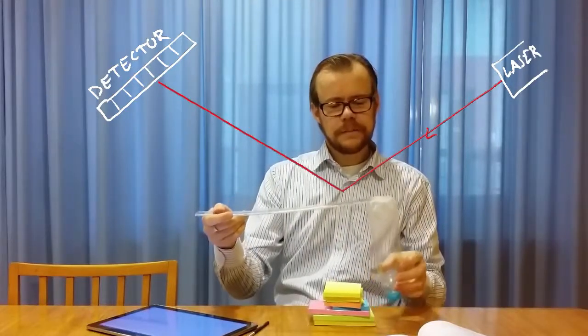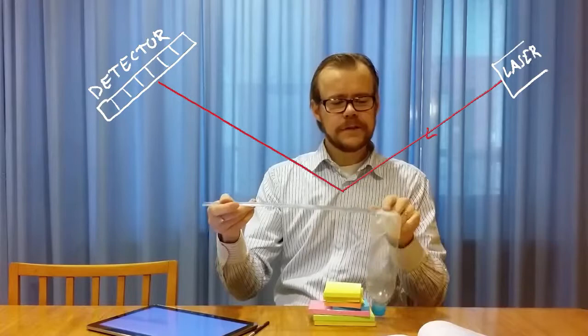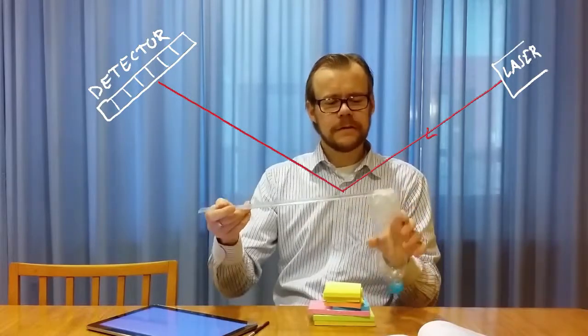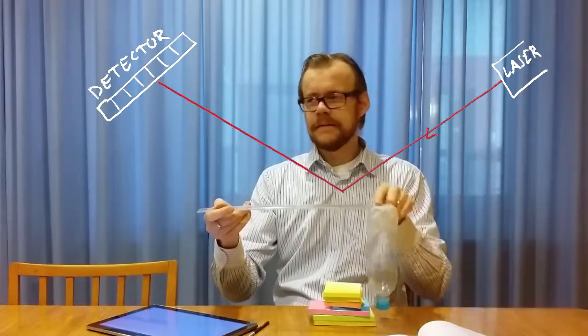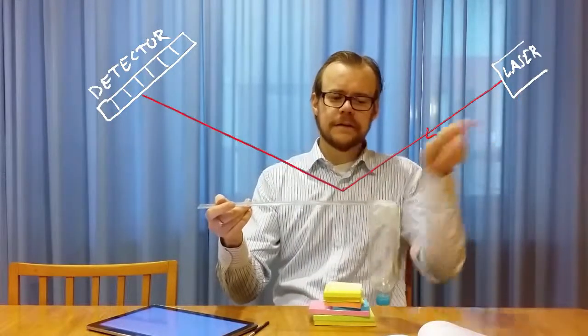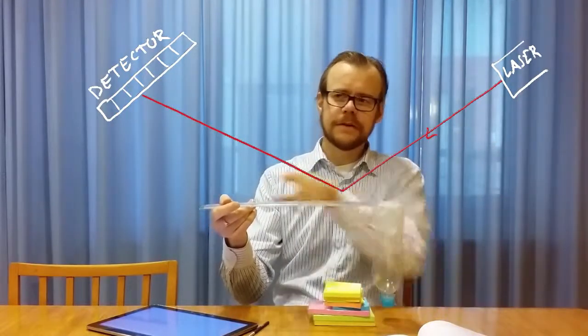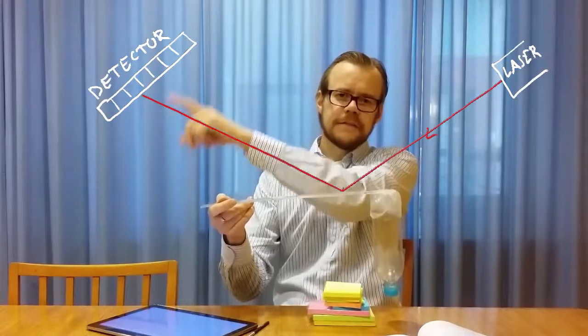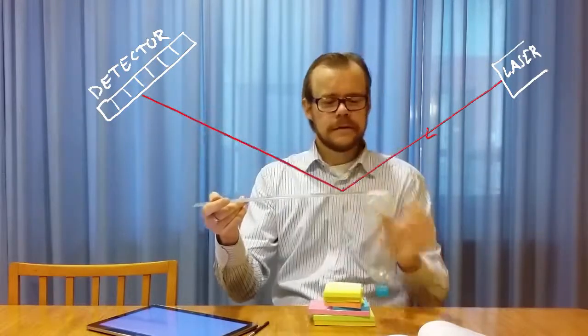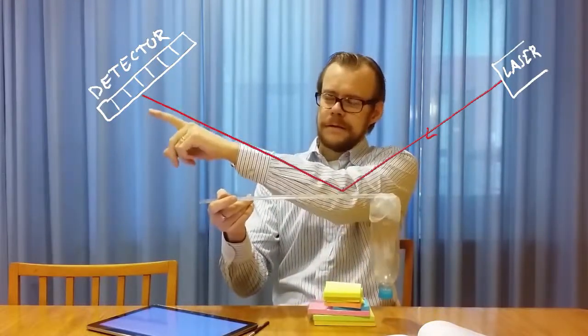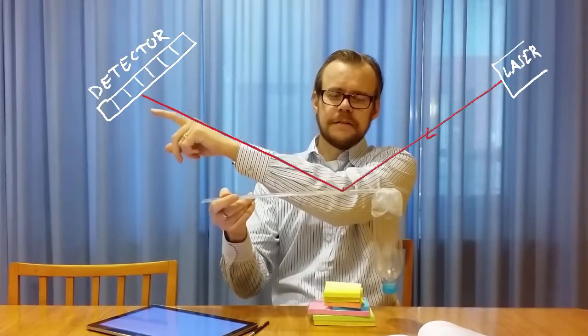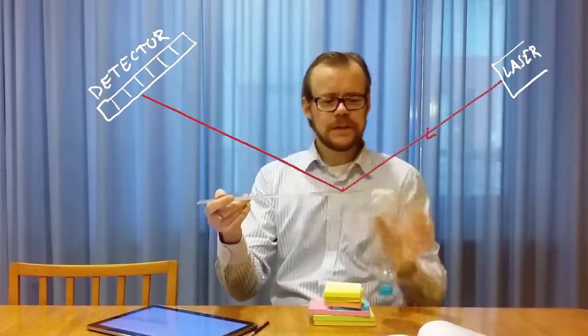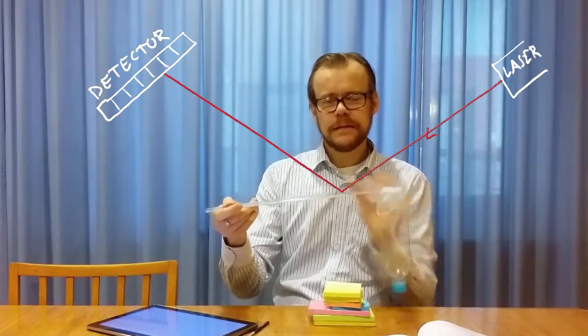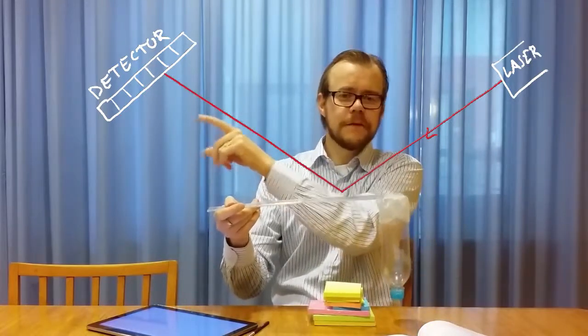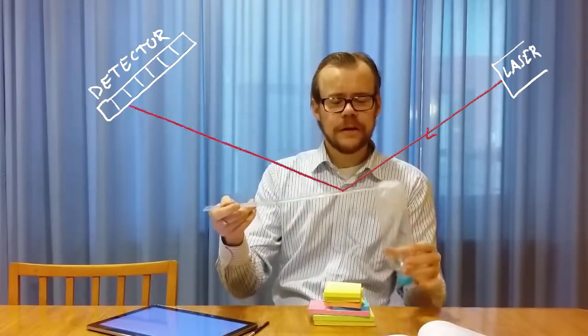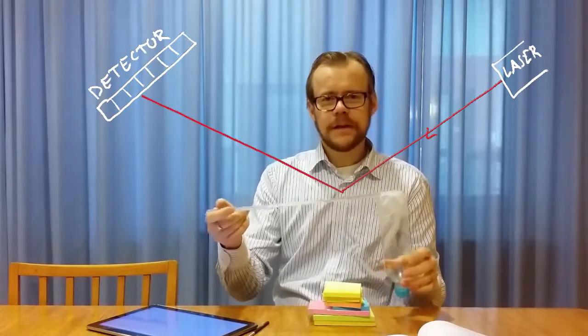Then you will see when the tip deflects up like this, it will change the angle of the surface. That means that the laser will take a different trajectory if we change the angle of this mirror. And that means that the location of the laser on this sensor side here will be at a different position if this deflects. And then that change in location will be directly proportional to the force on the cantilever. So then we can measure the force.